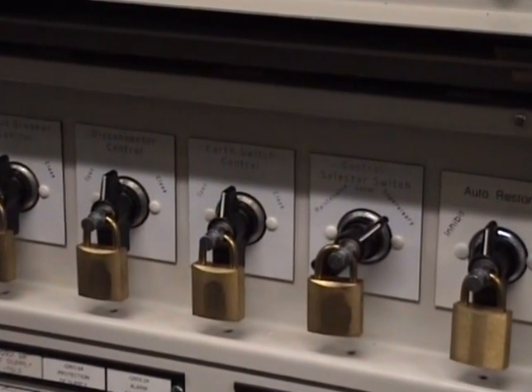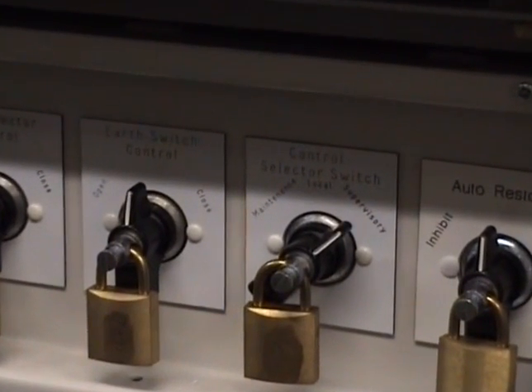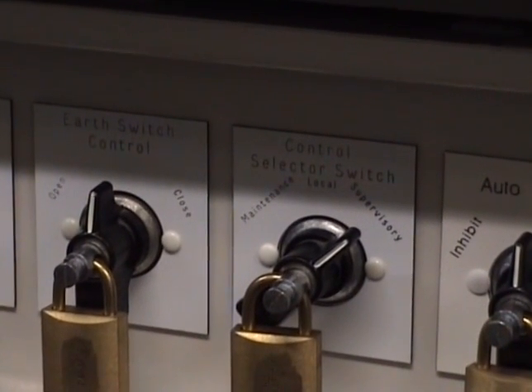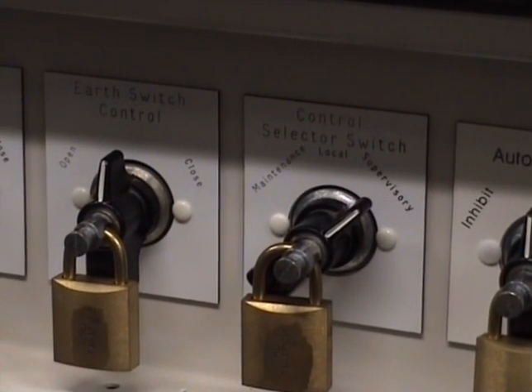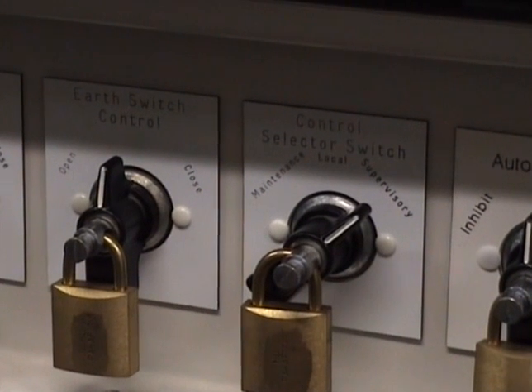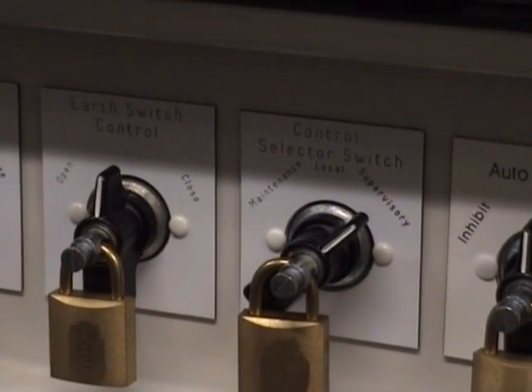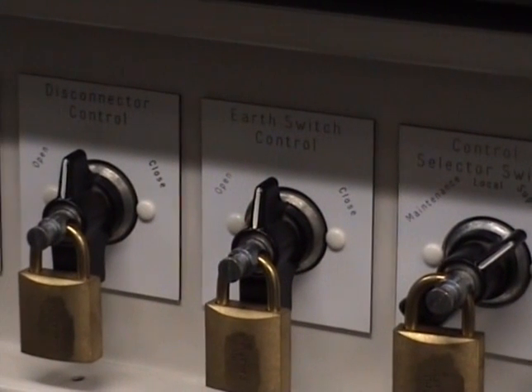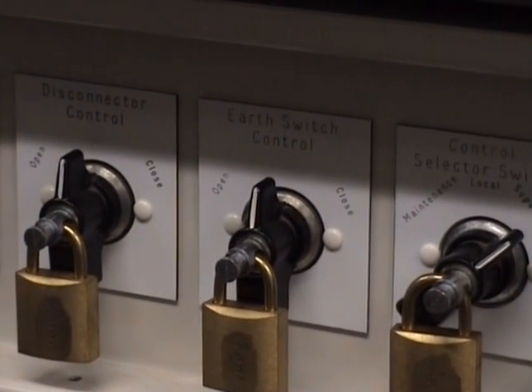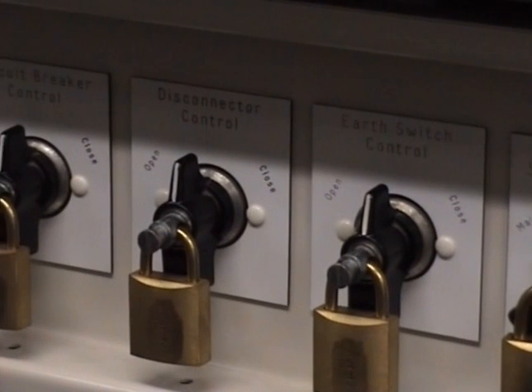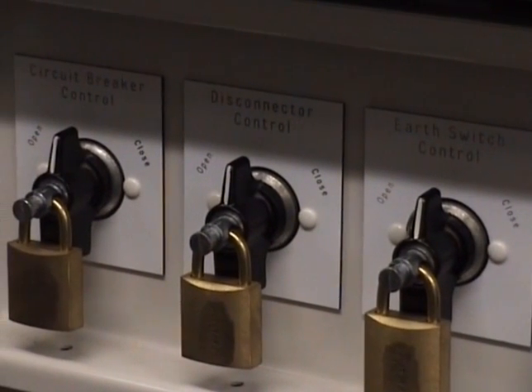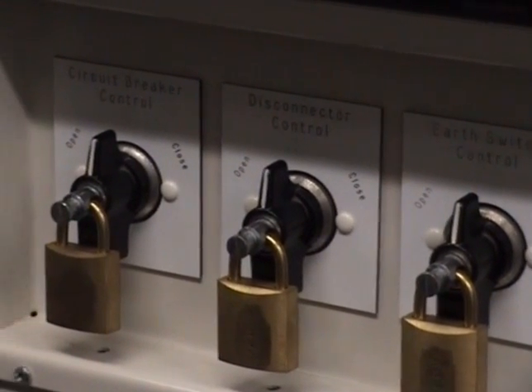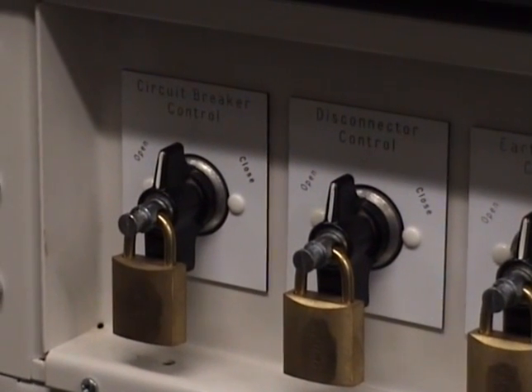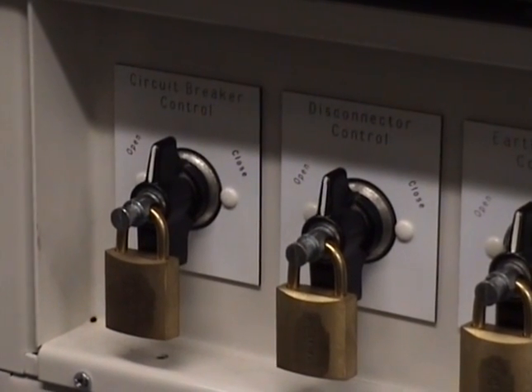On the right we see the supervisory local switch, which gives the control of the circuit breaker either to the electric control room or to a local operator. The earth switch control opens or closes the earth switch. The disconnector control opens or closes the disconnector, and the circuit breaker control opens or closes the circuit breaker.